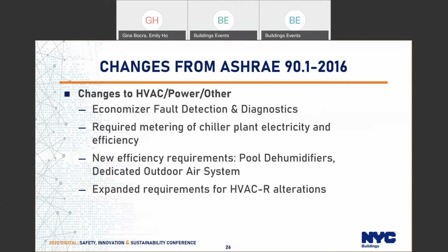There are new efficiency requirements. You'll see new efficiency tables added within the HVAC section. Some of that equipment includes pool dehumidifiers and dedicated outdoor air systems. So there are new moisture removal efficiency requirements for the dedicated outdoor air systems. Also in 90.1, we think this is a really important addition to the code. For alterations, there's a new section for HVAC alterations, and the requirements are greatly expanded. Instead of the code being applicable to essentially whatever the scope of the work is, as it has said in the past, it details a list of sections that are required and certain controls that are required for that HVAC alteration.